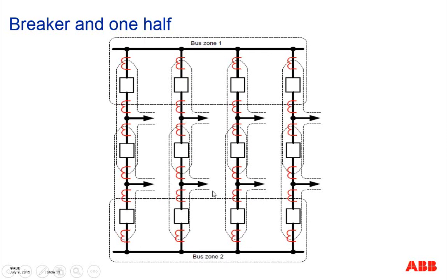So this can be a transformer, a line, a reactor, or a capacitor, but anyway, they have all been properly protected. You don't really need a dedicated busbar protection for them, but you need a dedicated busbar protection for the main two busbars.